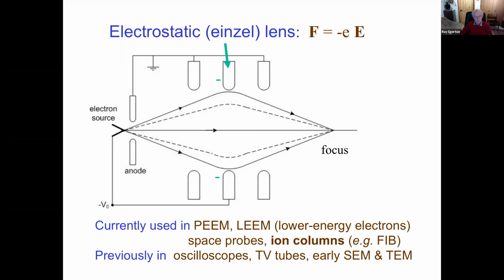And these lenses are currently used in photoelectron microscopes and low energy electron microscopes, where we're talking about 10 kV accelerating potential typically. Electrostatic lenses are also used in space probes, where weight is a prime consideration. They're also used in ion columns, such as a FIB machine, because the magnetic force is proportional to the speed of the charged particle, and ions travel much slower than electrons for a given accelerating potential. And so it's inefficient to focus ions with magnetic fields. Instead, a FIB machine has an electrostatic column.